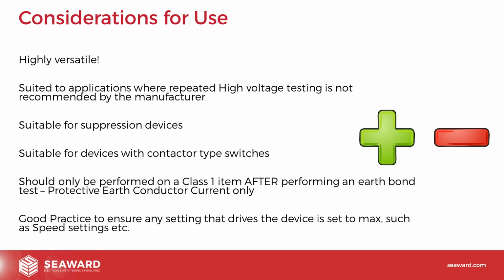It's absolutely suitable for suppression devices, because again we're performing the test at mains voltage, so 110 or 240 volt, so we're not going to trigger any of the surge protection within these sort of devices. It's completely suitable for devices with contactor type switches, the caveat being that we have to switch them on. So we apply power, we press the main switch, the unit then powers up. We then can be sure that the entire circuit is engaged, and therefore any leakage will be representative of the product under test whilst it's operational.